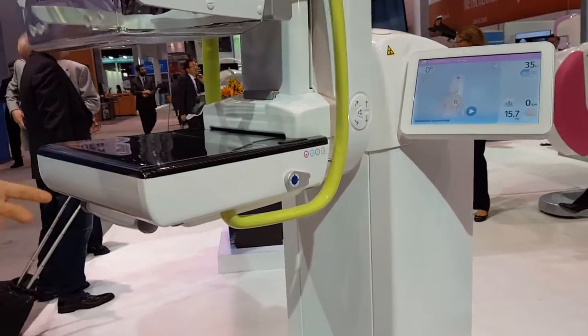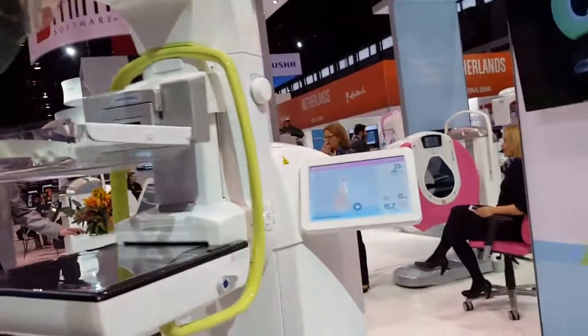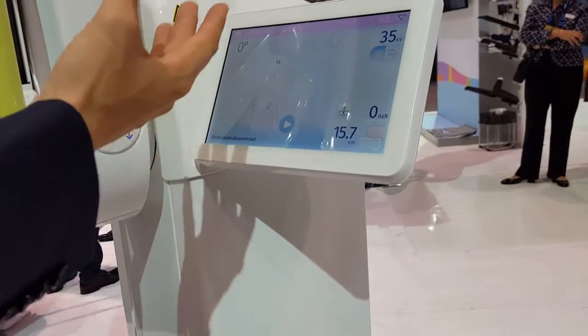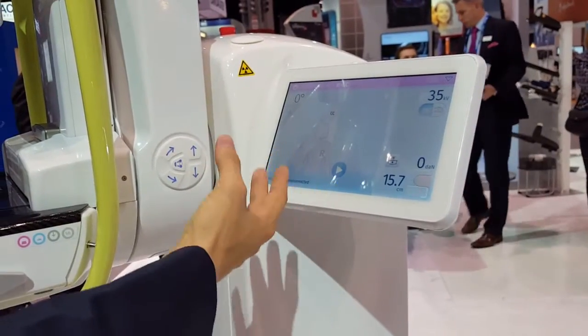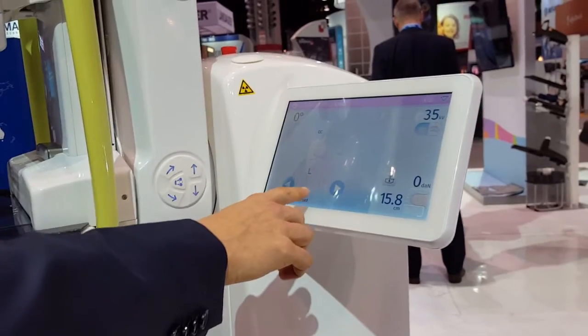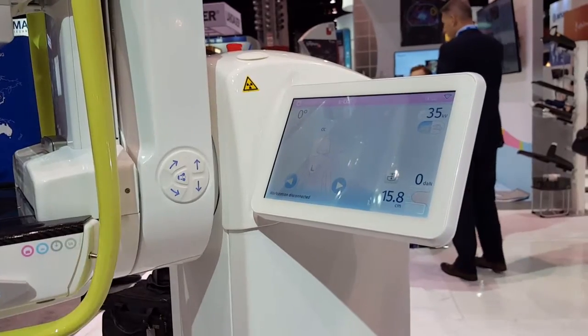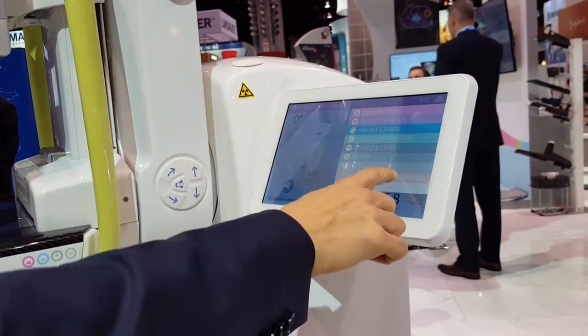The design philosophy is to make compact, easy-to-use, robust units that look good, but also so radiographers enjoy using them and have an easier time. This screen is called the Planmed Clarity Flow system. Here you can configure the unique workflow — for example, a radiographer starts with the right CC view, presses play, and the unit automatically drives to the following view. You don't have to run back and forth between the workstation and the unit, and everything can be configured from the service and configuration menu.